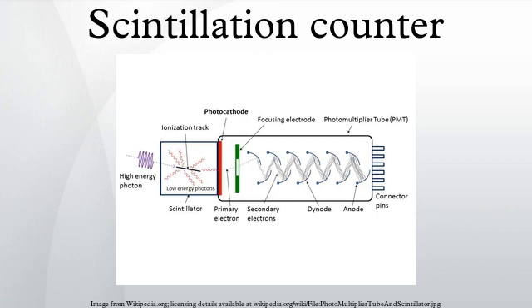The impact of a single electron on the dynode releases a number of secondary electrons which are in turn accelerated to strike the second dynode. Each subsequent dynode impact releases further electrons, and so there is a current amplifying effect at each dynode stage. Each stage is at a higher potential than the previous to provide the accelerating field.